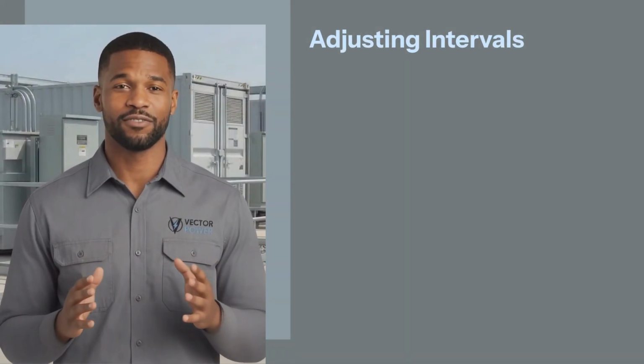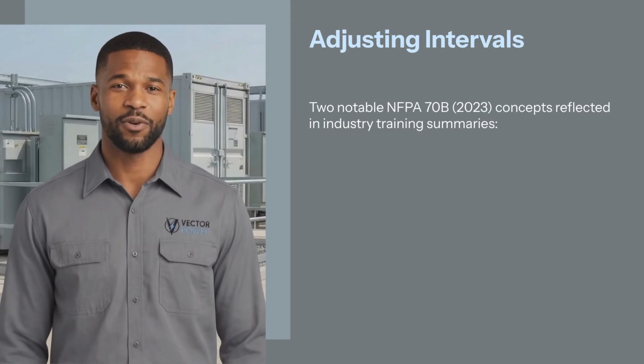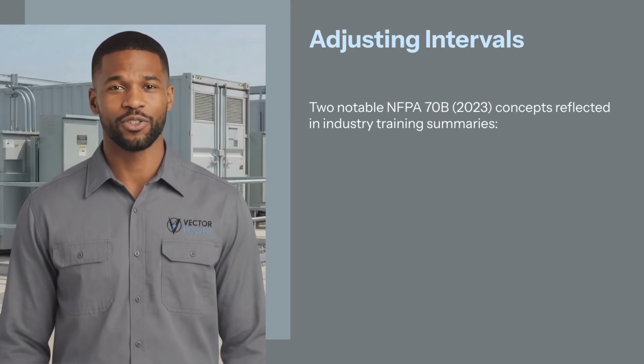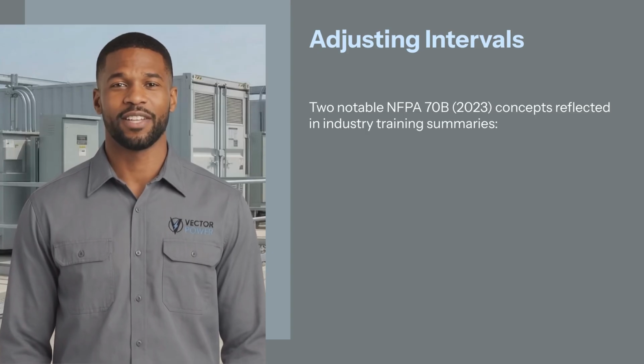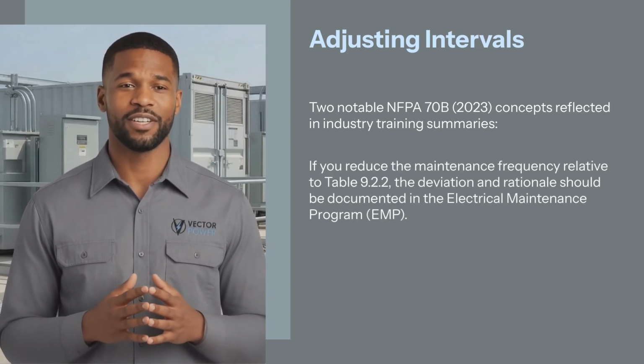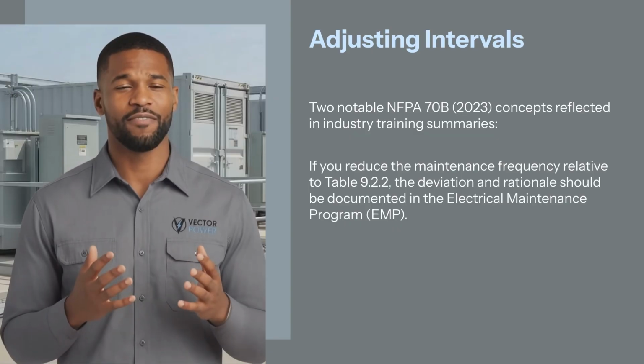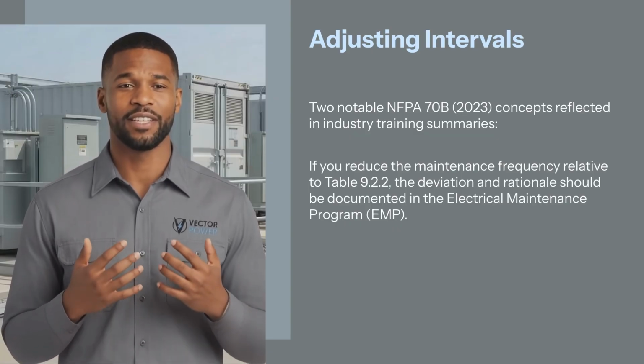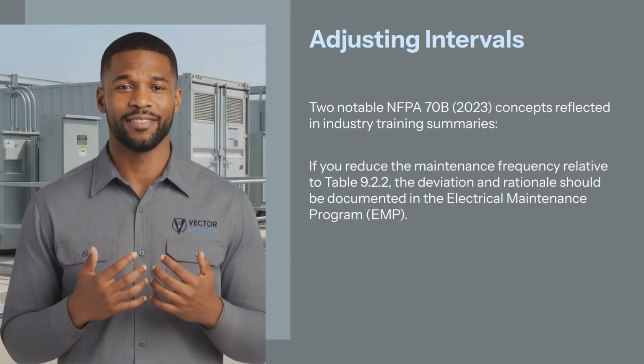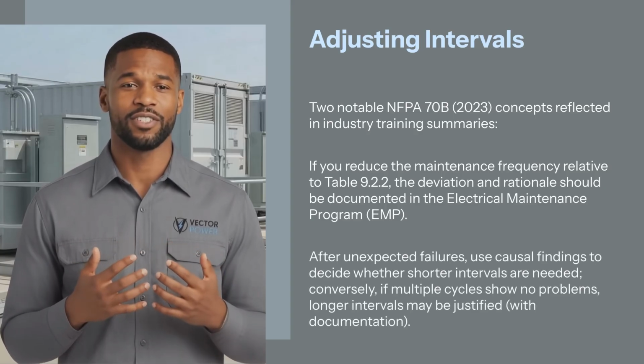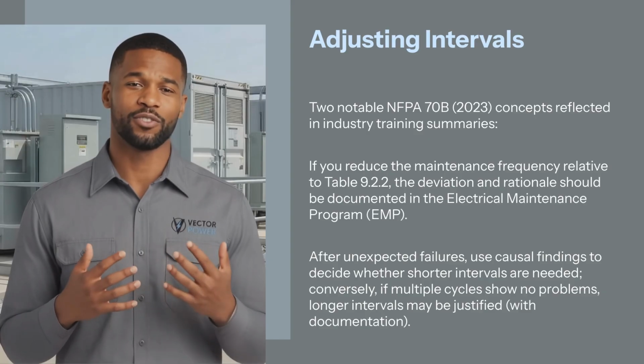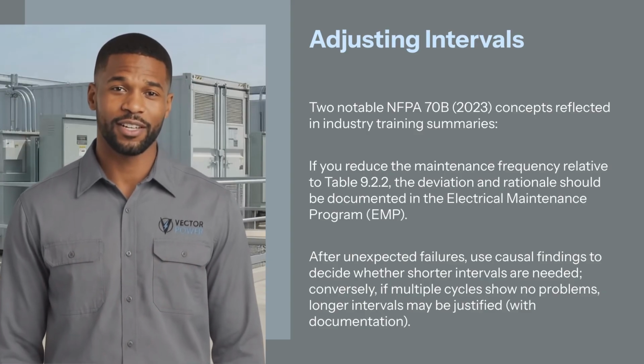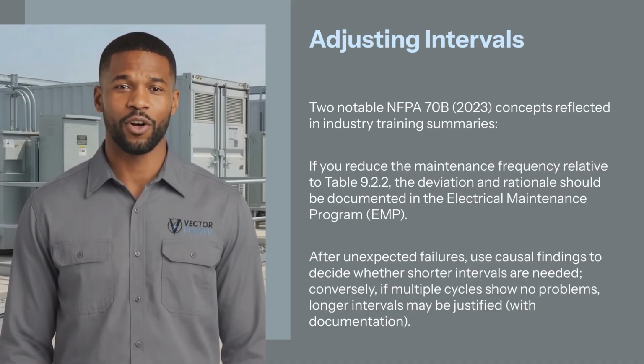Adjusting intervals. Two notable NFPA 70B 2023 concepts reflected in industry training summaries. If you reduce the maintenance frequency relative to Table 9.2.2, the deviation and rationale should be documented in the Electrical Maintenance Program, EMP. After unexpected failures, use causal findings to decide whether shorter intervals are needed. Conversely, if multiple cycles show no problems, longer intervals may be justified with documentation.